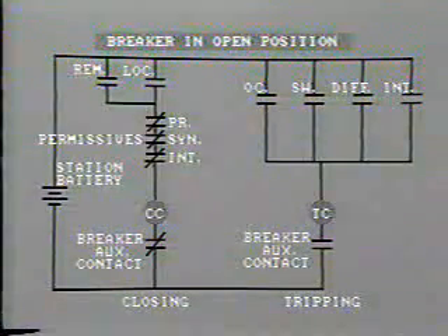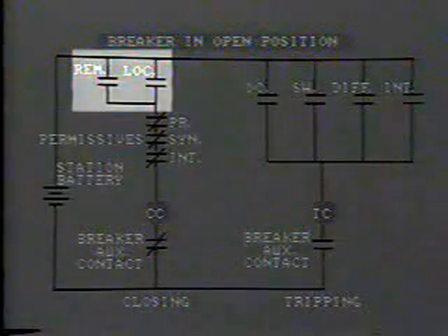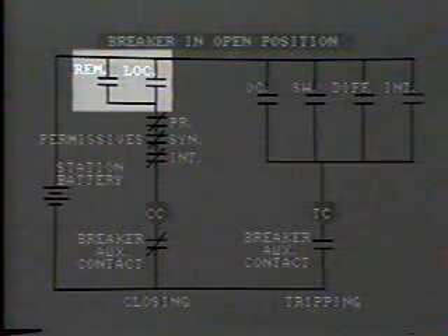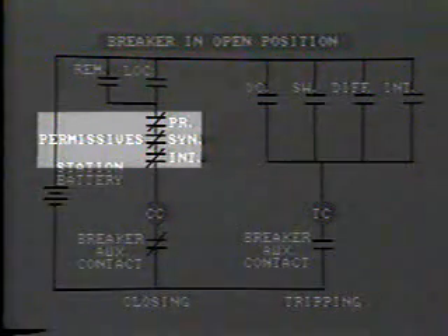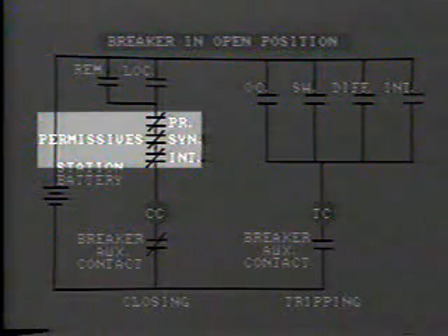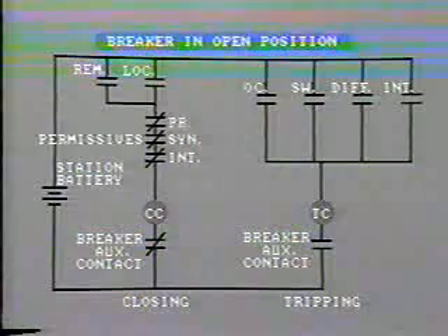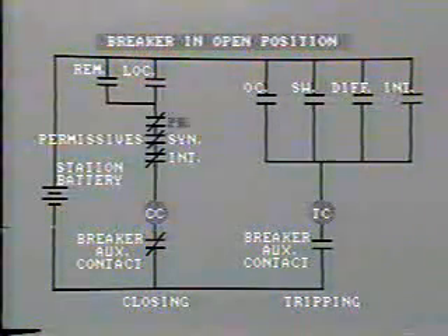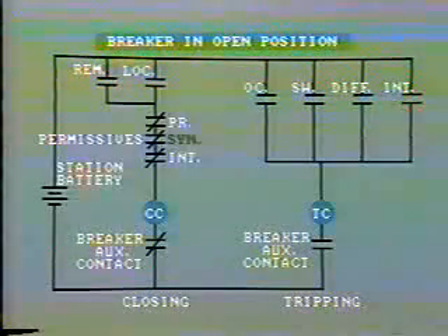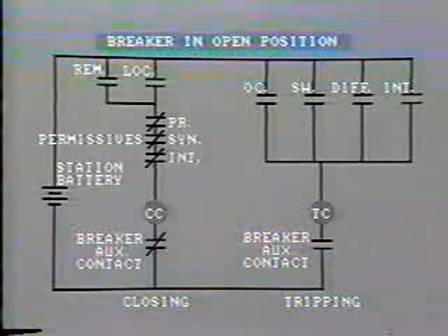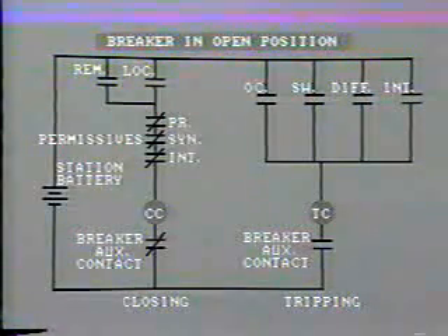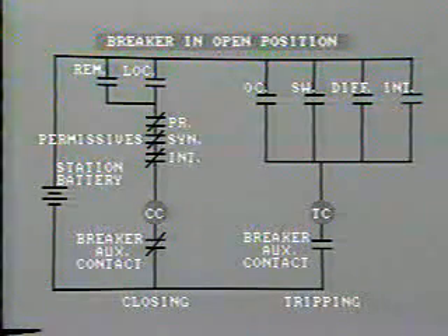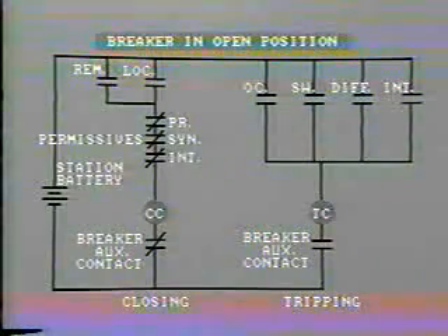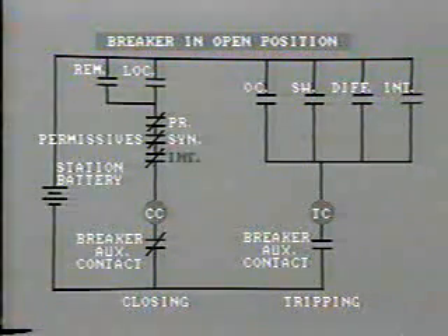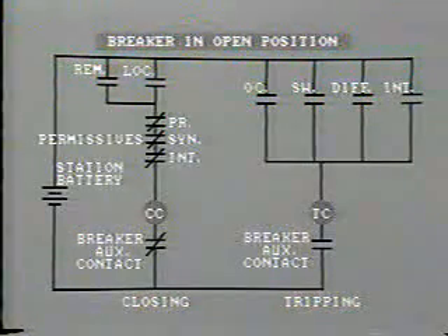You would think that to close the breaker, it would be sufficient to close any pair of the manual switching contacts. In this installation, we have local and remote operation. But look, there are other contacts in series with the closing coil, and these are known as permissive contacts. For example, this pair will only close when there is adequate pneumatic pressure available to operate the breaker mechanism. This pair of permissive contacts are only closed when a synchronizing relay determines that conditions are correct for closing. And yet another pair only close when there is no remote inter-tripping signal on the system. I'm sure you can think of a lot more permissive conditions.